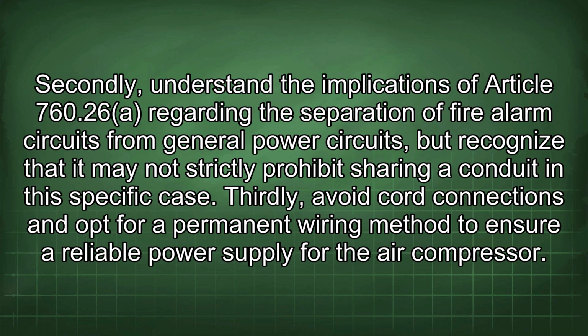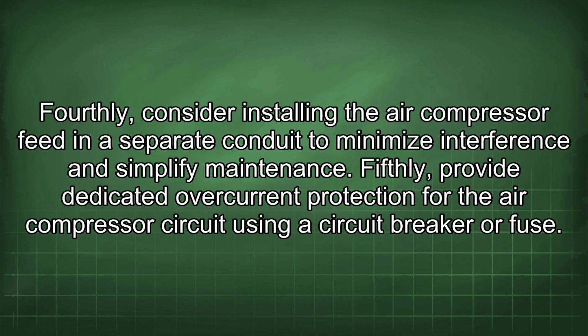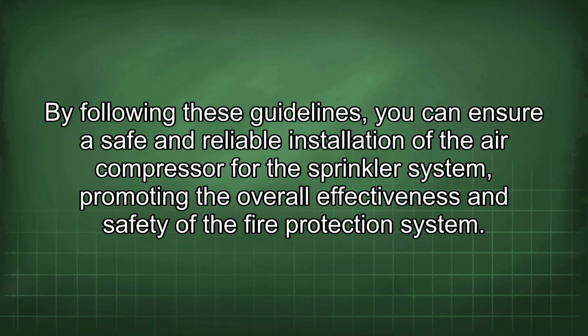Thirdly, avoid cord connections and opt for a permanent wiring method to ensure a reliable power supply for the air compressor. Fourthly, consider installing the air compressor feed in a separate conduit to minimize interference and simplify maintenance. Fifthly, provide dedicated overcurrent protection for the air compressor circuit using a circuit breaker or fuse. By following these guidelines, you can ensure safe and reliable installation of the air compressor for the sprinkler system, promoting the overall effectiveness and safety of the fire protection system.